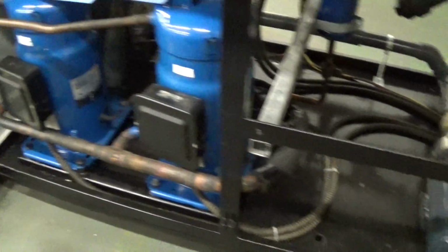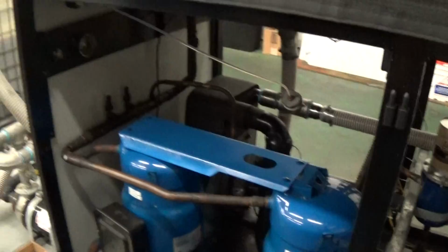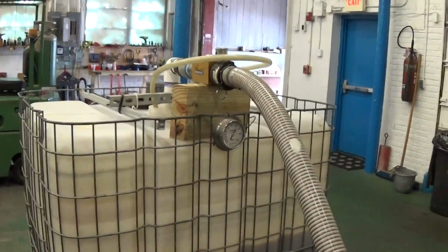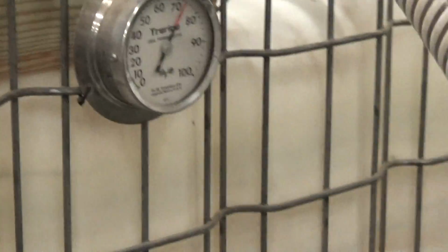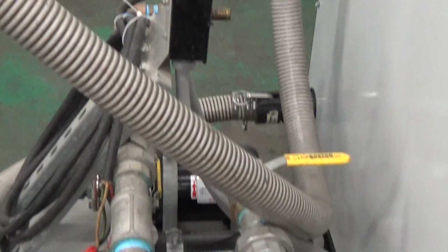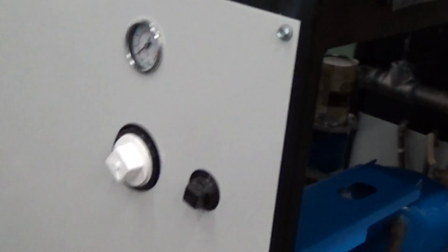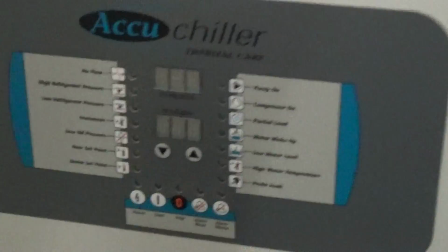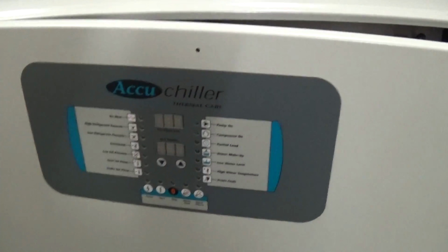This has 2 scroll compressors, 10 horsepower Danfoss. And what we've done is we've painted the entire base of the unit, removed the tank, and we have it set up with our test tank here, which is right about at a little over 70 Fahrenheit right now. We don't have to use the pumps for this particular test today. And we have a brand new gauge, and we also bought these Velcroed-on coil covers, brand new from Permatron, I think it is, and also a brand new touch display here, or the overlay, I should say.